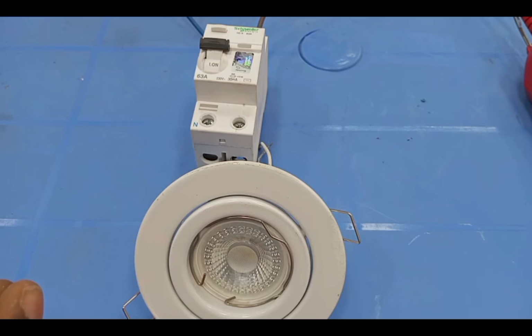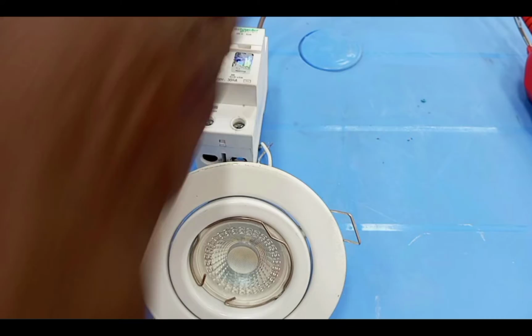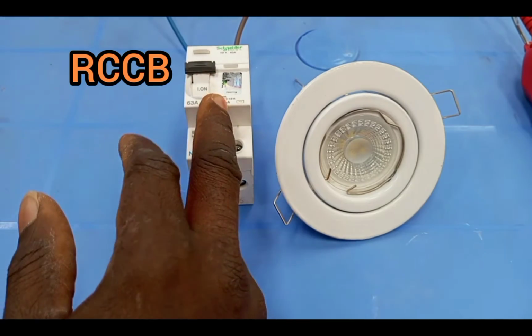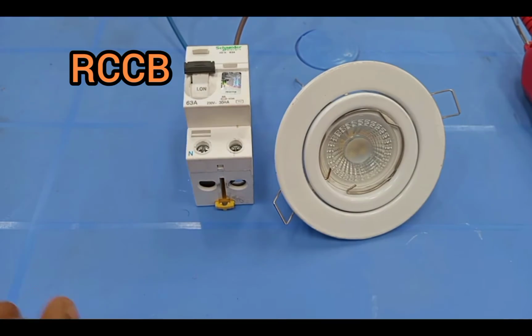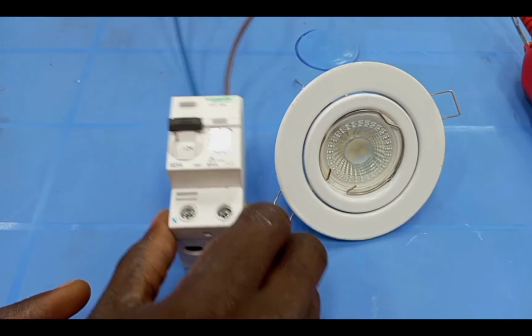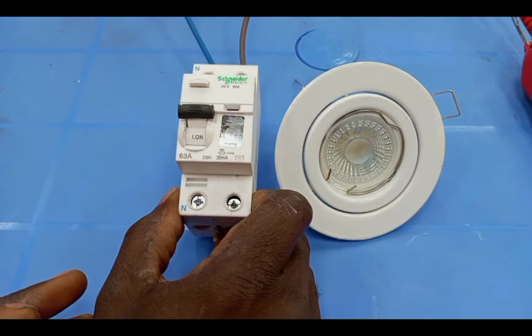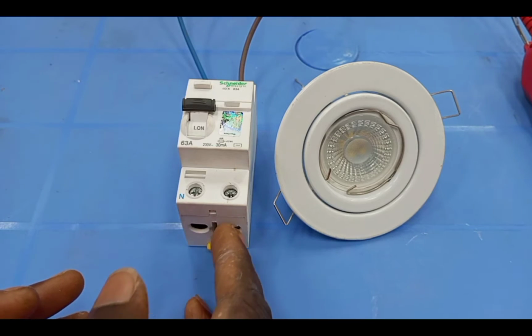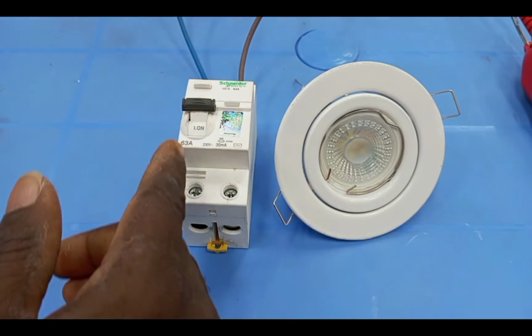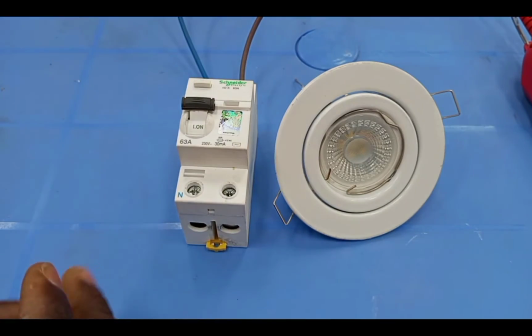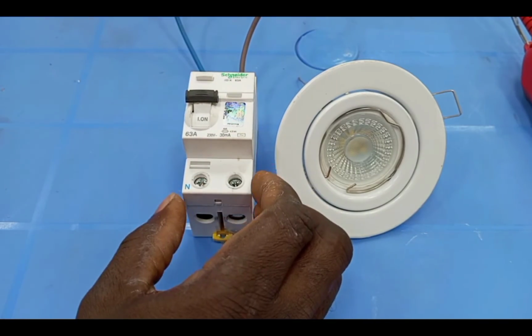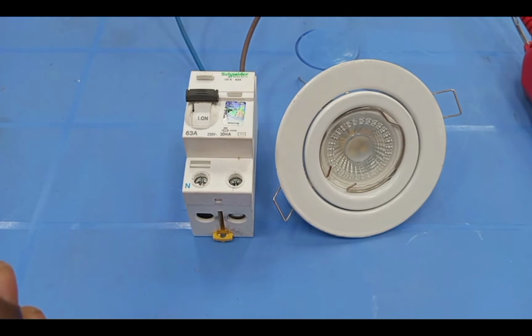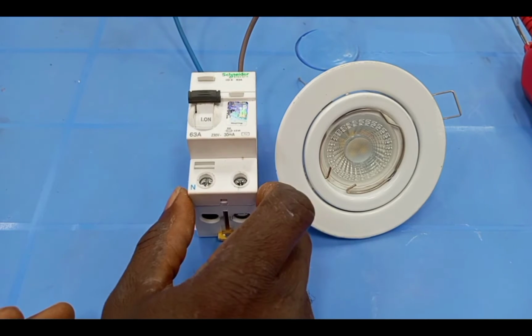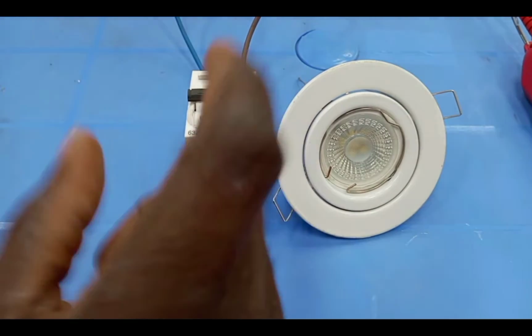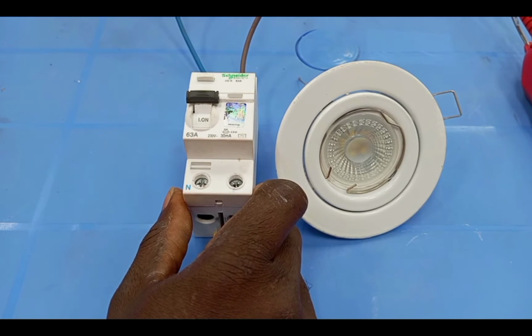And so the moment an amount of current that is more than 0.03 amp flows through the live wire, then the RCD will trip. It cannot trip when there is overload. It can also not trip when there is short circuit. Now, this 63 amp rating you are seeing here is just telling you the amount of current that this contact can carry. It doesn't mean that when 63 amp flows through it, it will trip. No. So you should make sure that whatever load you are connecting to this RCD altogether shouldn't be more than 63 amps. And so when you are using the RCD, in this case RCCB, you can't use only this one as the main breaker.